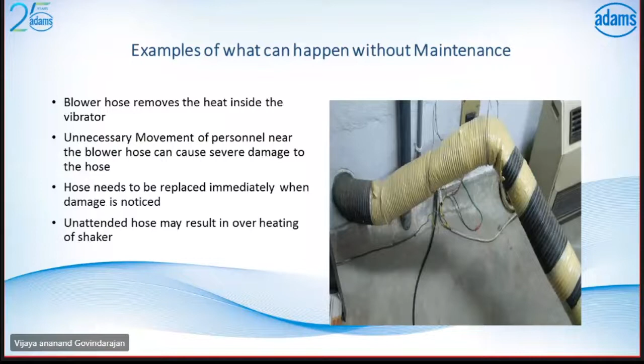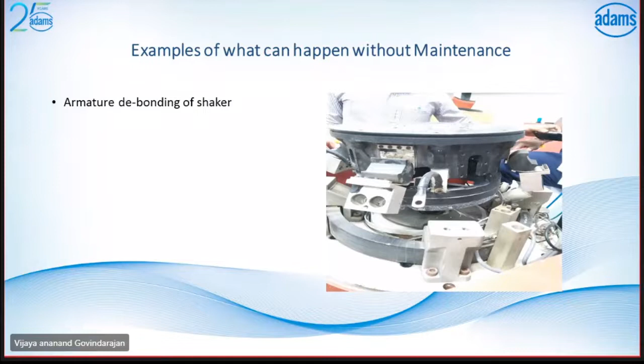The armature is a cylindrical coil that is fixed to a magnesium body through some special bonds. If the armature is not properly cooled, that may result in debonding of the armature. The slip table needs to be removed and maintained frequently. If the mounted load is not balanced, if the bolts we use are excess in length, if excess turning moment is applied, or if the drive bar coupling to the slip table is damaged, then that may cause bulges in the slip table.